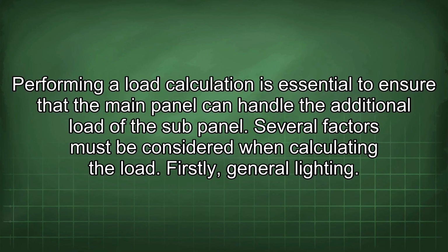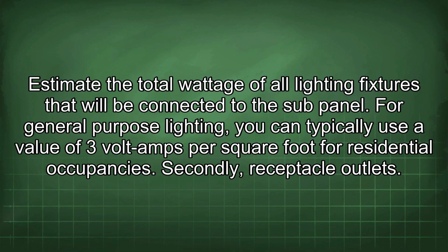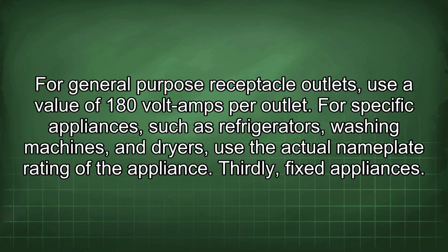Firstly, general lighting. Estimate the total wattage of all lighting fixtures that will be connected to the sub-panel. For general purpose lighting, you can typically use a value of 3 volt amps per square foot for residential occupancies. Secondly, receptacle outlets. For general purpose receptacle outlets, use a value of 180 volt amps per outlet. For specific appliances, such as refrigerators, washing machines, and dryers, use the actual nameplate rating of the appliance.